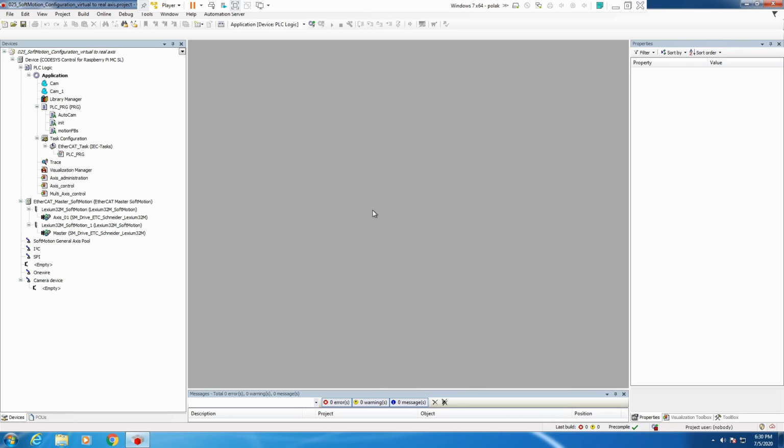The third thing is that your master and slave needs to have exactly the same units and needs to be properly scaled. For example, if you have millimeters feeding the material, then you need to have the same units which are based on linear speed of top of the blade of the knife, because you want to cut it on the fly and you don't want to mess it up. First of all, we have our master and slave axis exactly in the units what we want. We say degrees, and our example is going to be in degrees.